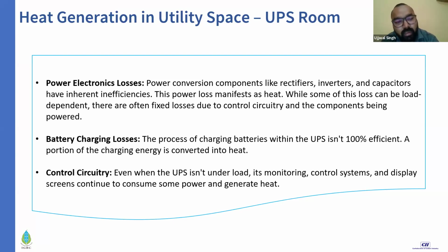91.8% efficient. But apart from the UPS, you charge your batteries whenever you discharge them as well. Both charging and discharging a battery are not 100% efficient and generate some heat. Even self-discharge happens in the battery, contributing some heat load to the data center, and this should be accounted for when calculating the cooling system size for the UPS room.